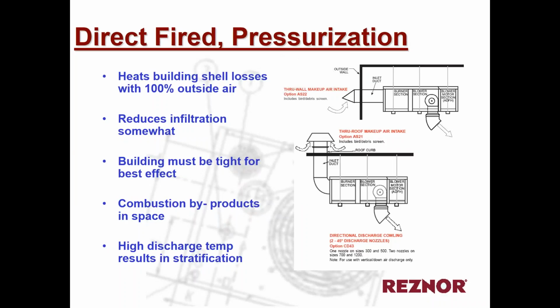That leads us to the direct fired pressurization units. One of the names that you'll hear sometimes a lot is a Cambridge unit. That's what this unit is. The direct fired pressurization type unit is a direct fired unit that's bringing in 100% outside air to pressurize a space in order to heat it. There are some disadvantages to this. Because you're bringing 100% outside air in through this machine to heat a building, your temperature rises are much higher, which in some cases would require greater gas input to do that.